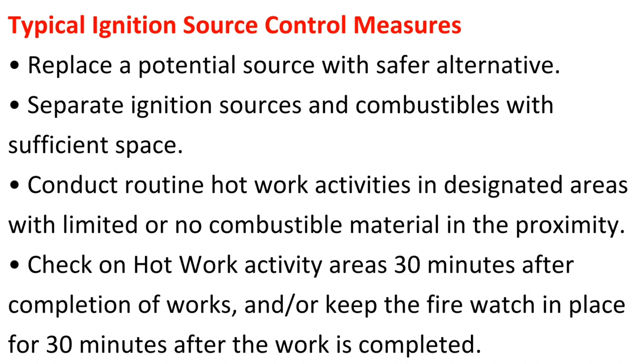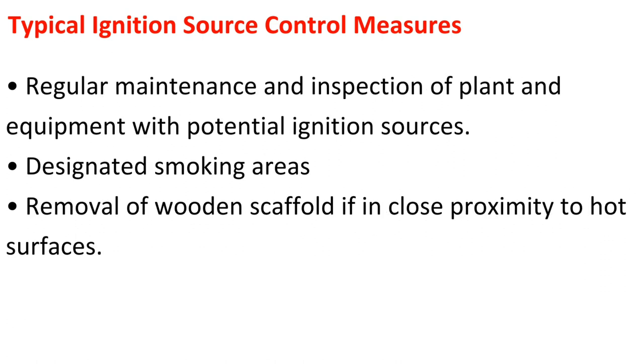Typical ignition source control measures include: replace a potential source with a safer alternative; separate ignition sources and combustibles with sufficient space; conduct routine hot work activities in designated areas with limited or no combustible material in the proximity; check on hot work activity areas 30 minutes after completion of works, and/or keep the fire watch in place for 30 minutes after the work is completed; regular maintenance and inspection of plant and equipment with potential ignition sources; designated smoking areas; and removal of wooden scaffold if in close proximity to hot surfaces.